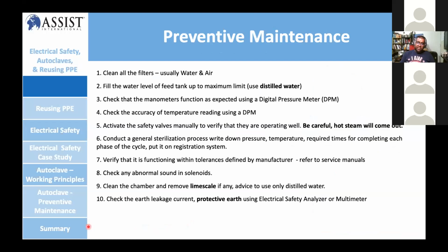For preventive maintenance, always clean all the filters, usually the water and air line filters. Use water and air pressure to clean all the lines and the filters. Fill the water tank up to the maximum limit. Always make sure you use distilled water, because most of these autoclaves are designed to work on distilled water. If you use normal water, the lifespan is reduced, and I can show you later what normally happens.